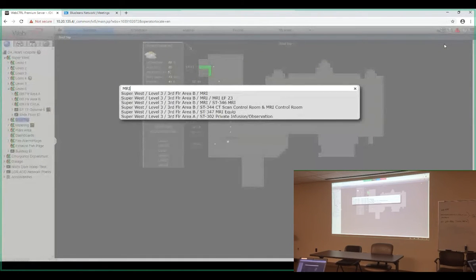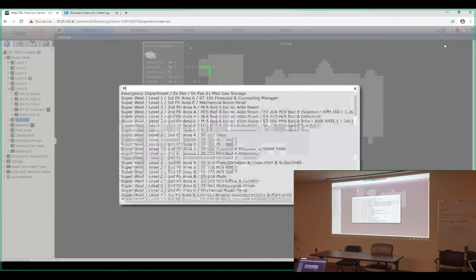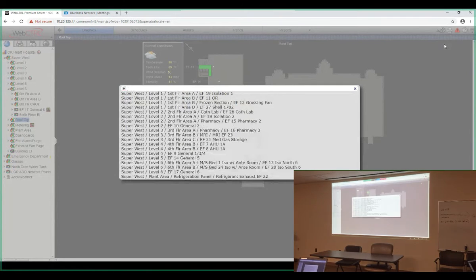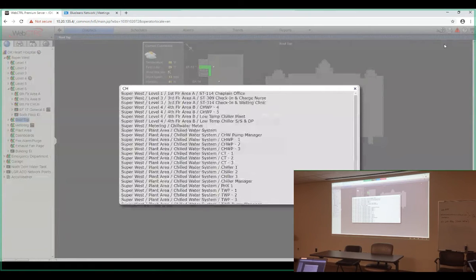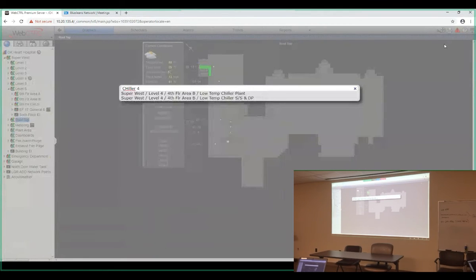So if you don't want to navigate to something, you can use this find feature to instantly jump to somewhere in the system. All it's doing is looking at the geographic tree name to direct you there. So if we wanted to look for an exhaust fan 18, you can start typing EF. Here's 19, 11, 18. So it's very sensitive to the context, so it's EF space 18, but I usually just start typing CH until I find what I'm looking for.